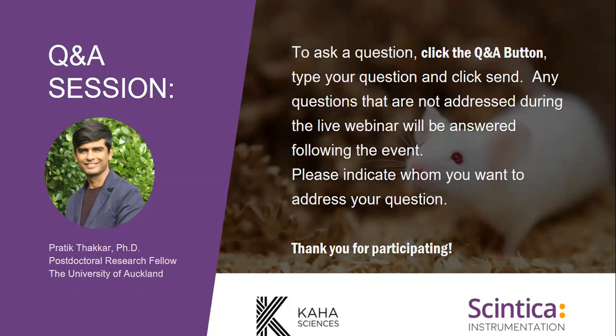Great answer. The telemeters that you used, Pratik, were they single use or reused for your multiple experiments? Right. The telemeters were reused multiple times, but the oxygen electrodes were replaced between uses. Every time, I make my own electrodes and pass the calibration, reattach and pass the calibration again, and then use it. I always check the offset and drift. Anything that happens, I have to check everything before implantation.